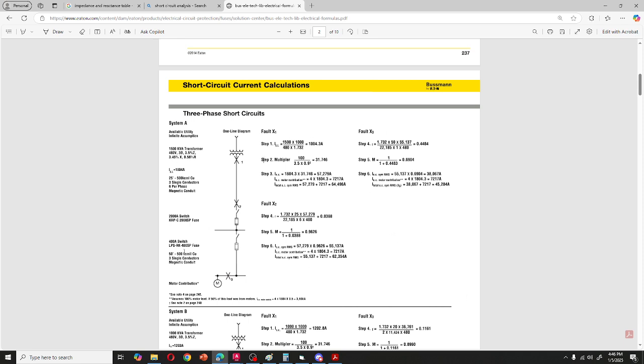This is just the list of what's involved from the post then to your load side. So 1,500 times 1,000 since that's KVA, divided by 480 for the voltage going down, times 1.732 since this is a three-phase load - that's the square root of 3. And you will get your ILL.